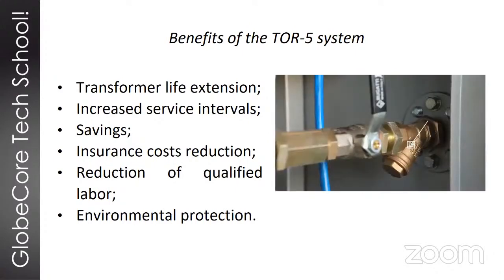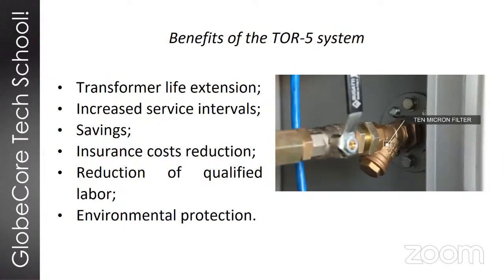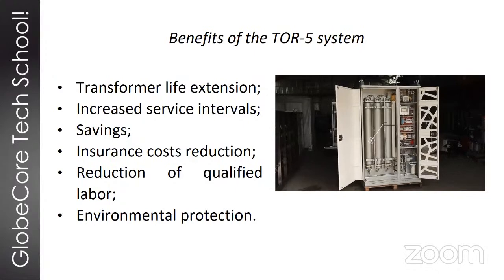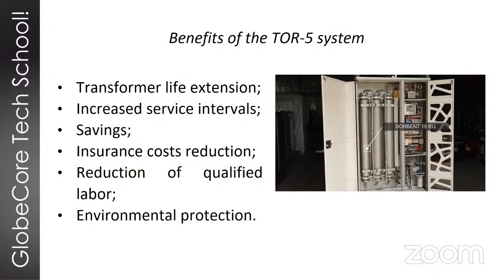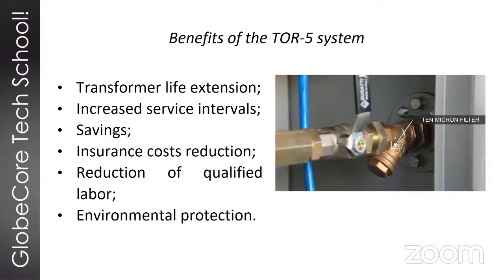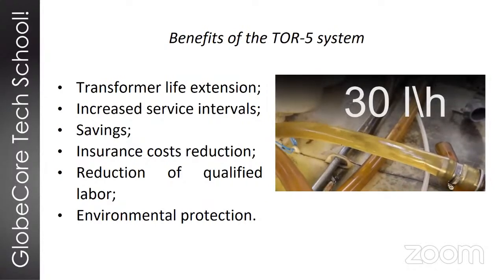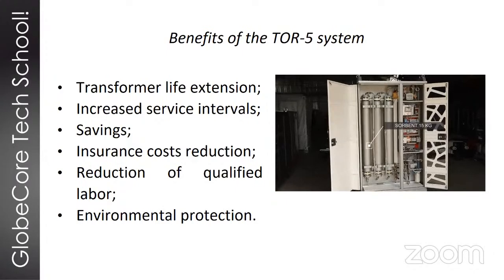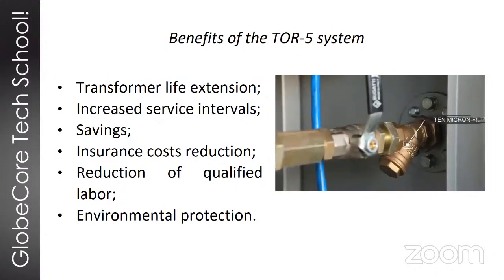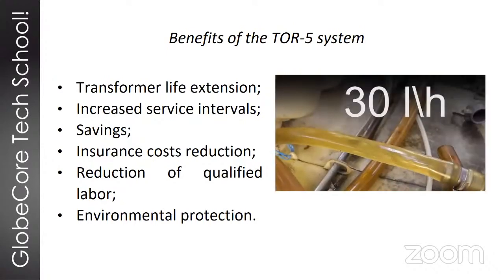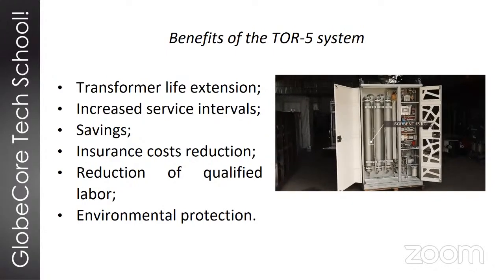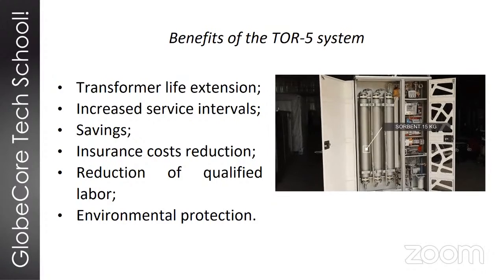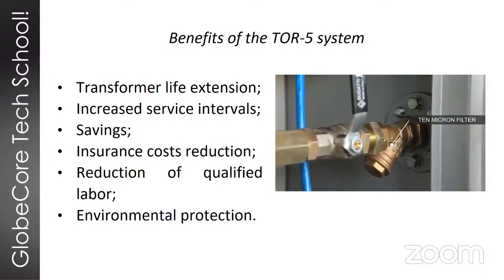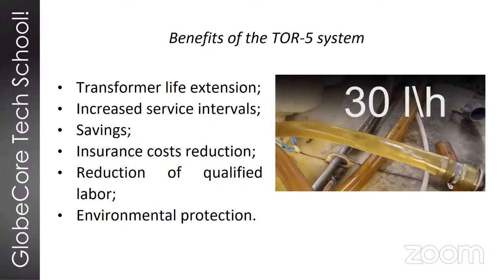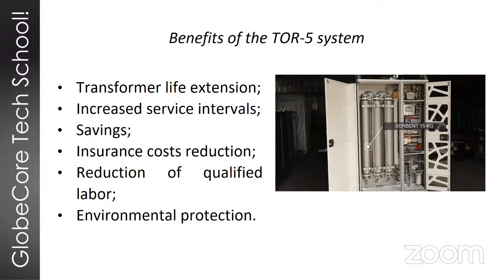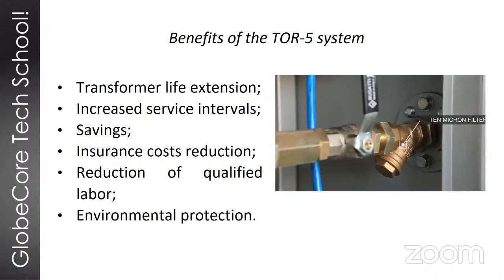Another thing is the reduction of the labor costs of the qualified personnel that you need to involve in transformer maintenance, such as people that take oil samples, or laboratory personnel, filtration equipment operators, and so on. So you would usually save on labor as well. One other important, last but not least, factor is environmental protection. When a transformer fails, if there is a leak or a fire or maybe an explosion even, that is usually an environmental disaster, even if a local one. So the TOR5 allows you to prevent such situations and eliminate any probability of environmental pollution that usually happens when transformers fail.